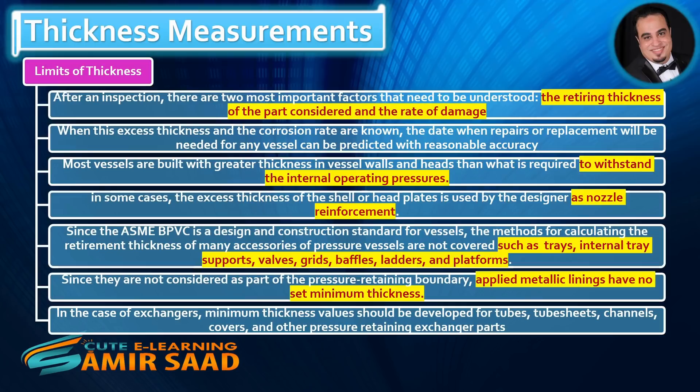Limits of thickness: After an inspection, there are two most important factors that need to be understood — the retiring thickness of the part considered, and the rate of damage. When the excess thickness and the corrosion rate are known, the date when repairs or replacement will be needed for any vessel can be predicted with reasonable accuracy.